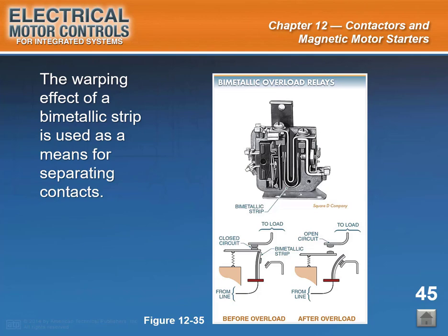Bimetallic overload relays operate on the principle of the bimetallic strip. A bimetallic strip is made of two pieces of dissimilar metal that are permanently joined by lamination. Heating the bimetallic strip causes it to warp because the dissimilar metals expand and contract at different rates. The resulting bend of the strip is used to actuate a set of switching contacts that indirectly disconnect power to the motor to protect it. End of slide 45.